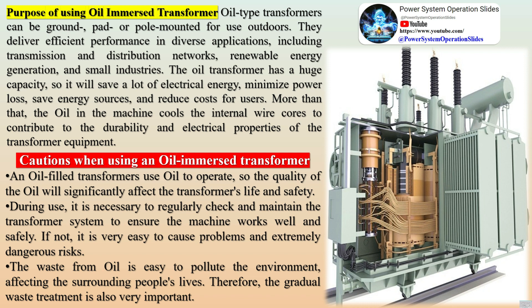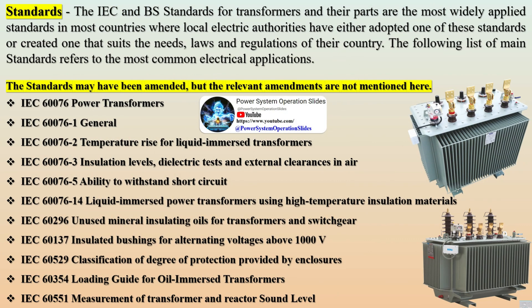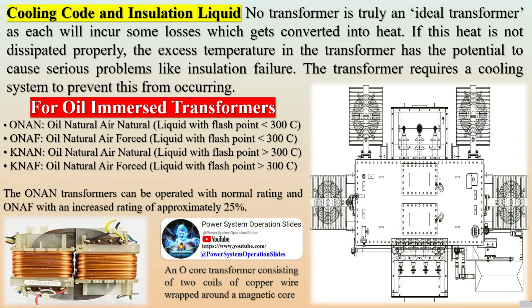An oil-filled transformer is structurally similar to a standard transformer and is classified according to the form of core insulation. It has the identifiable feature of oil-immersed coils to lower the heat of the devices within it. The basic elements consist of the magnetic core, windings, and bushings. The magnetic core provides a path for magnetic flow. Windings create a magnetic field and consist of a conductor coil wrapped around the core and insulated with pressboard barriers and screens. The thickness of the winding insulation increases with voltage.